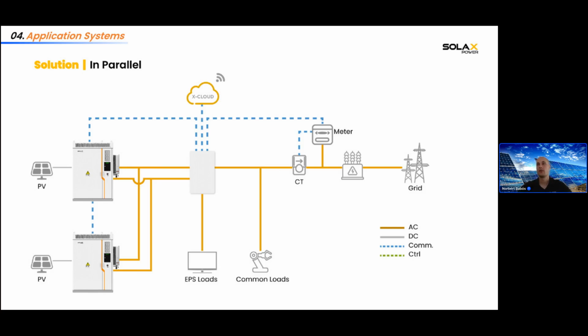And also when you have the grid, you can support the common loads on the grid side, and if needed, you can feed electricity back to the grid. And for this scenario, you also need the meter with CTs. So not just the CTs, also the meter.